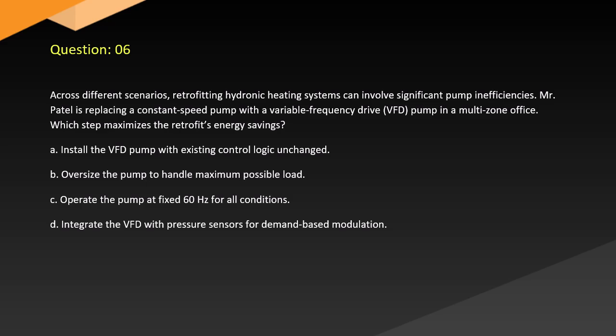Question 6. Across different scenarios, retrofitting hydronic heating systems can involve significant pump inefficiencies. Mr. Patel is replacing a constant speed pump with a variable frequency drive (VFD) pump in a multi-zone office. Which step maximizes the retrofit's energy savings? A. Install the VFD pump with existing control logic unchanged. B. Oversize the pump to handle maximum possible load. C. Operate the pump at a fixed 60 Hz for all conditions. D. Integrate the VFD with pressure sensors for demand-based modulation.